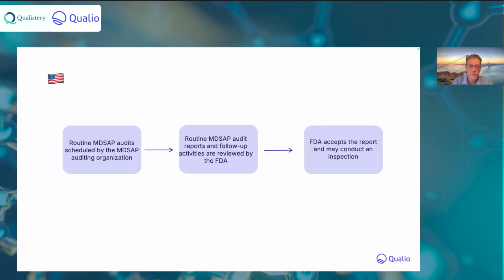Now in the US, as I mentioned earlier, the FDA was moving towards ISO 13485 implementation. That process will be completed in February of next year. FDA still conducts inspection if the results of the MDSAP audit are such that there's a doubt about the compliance and about the effectiveness of the quality management system. Also, FDA will conduct pre-approval inspections for PMAs. That's not something that's covered by the MDSAP program. But in general, FDA, and that is specifically CDRH, accepts and plays a very active role in the MDSAP process.